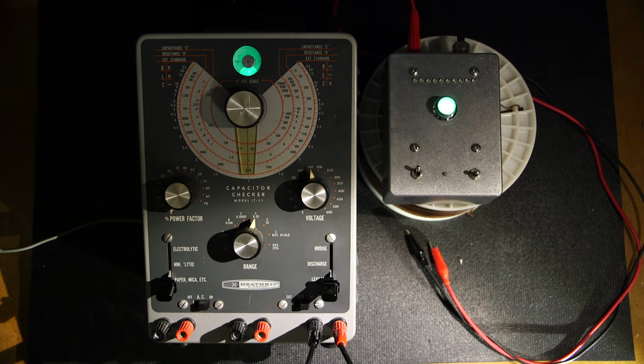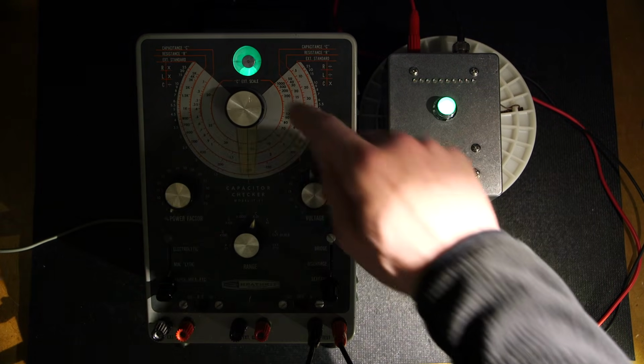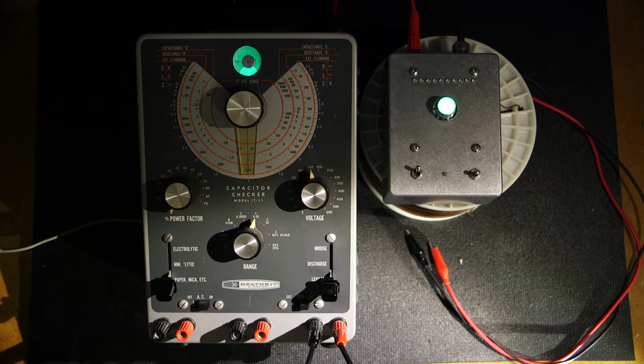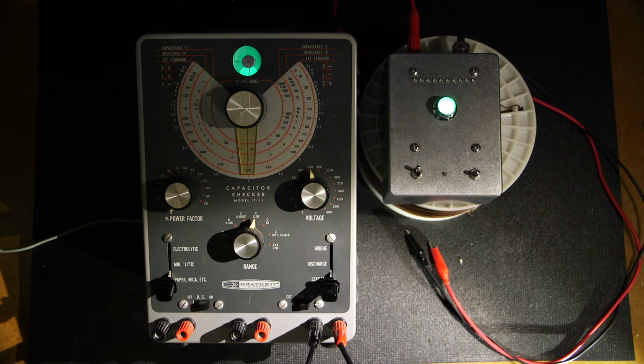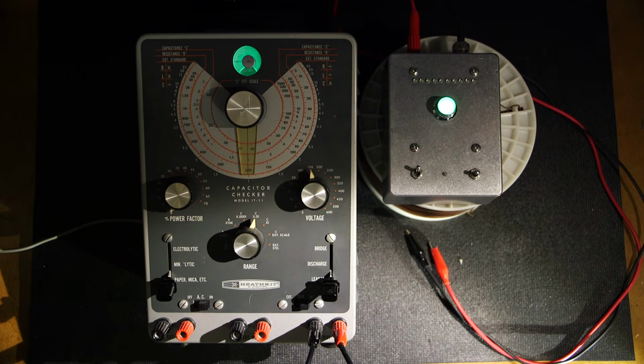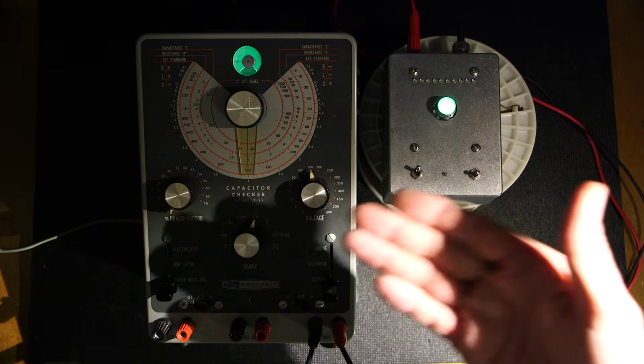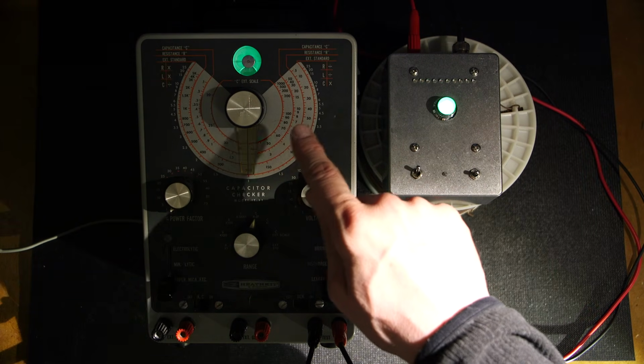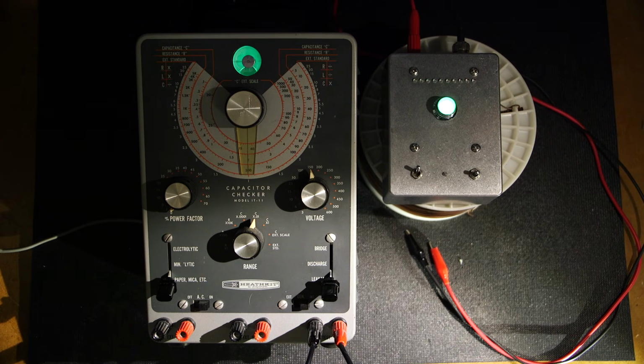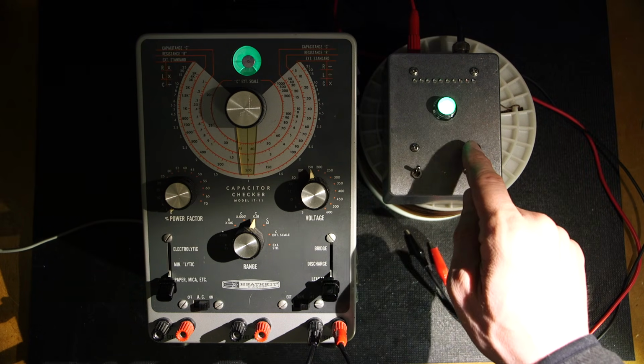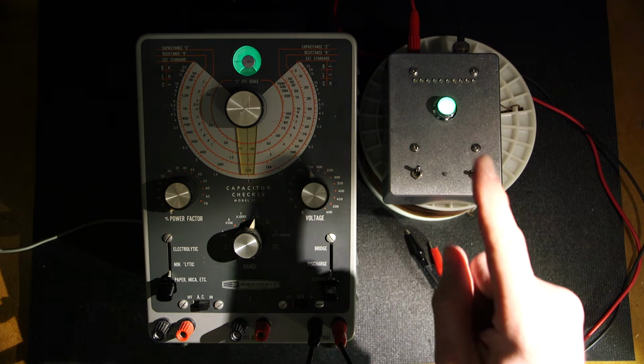Now the shadow angle is closed, and if you leave this hooked up for a long period of time it may open - oh, you can see it's actually trying to open now. It's the same with the other device: if left attached long enough, it'll most likely start to count down a little, as you can see here, but who knows how long that would take. It should be instantly open, so we'd know the capacitor is faulty, but it took 150 volts to show that with this tester, whereas the other one showed it's very bad instantly, with no movement at all at just battery voltage. So what's that telling us? We don't need high voltage to indicate leakage. I'll go grab another capacitor.